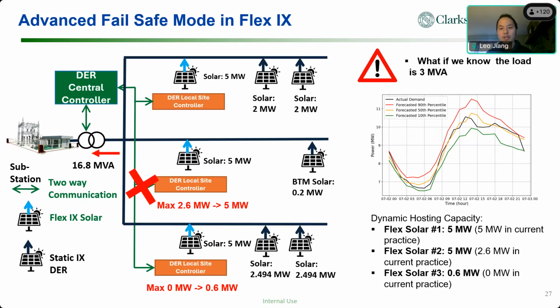But basically, how do you know the load? You can use a forecast plus a safety margin, or you forecast the load and add some additional conservative forecasting result to update your static hosting capacity. Then that will configure the local controllers there. So if you have 3 megawatt of load, for example, you can update the static hosting capacity to be the dynamic hosting capacity. Then your second solar farm will be allocated 5 megawatt of hosting capacity, because your total dynamic hosting capacity now is 10.6. In the third solar farm, instead of 0 megawatt hosting capacity, you can have 0.6 megawatt there.